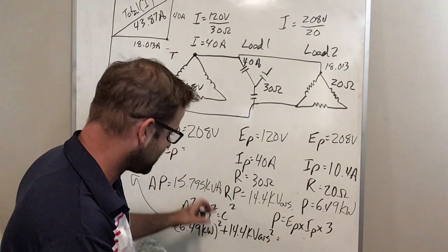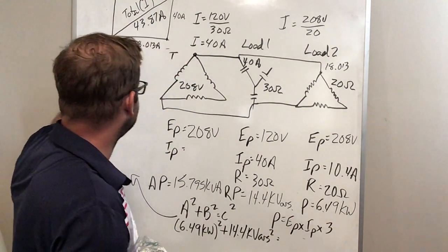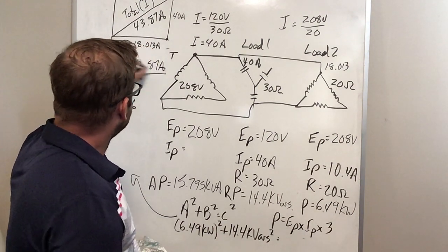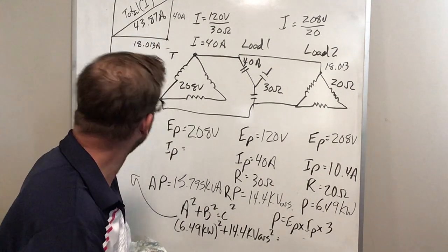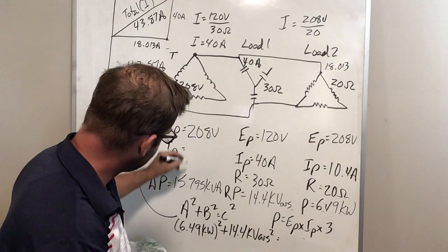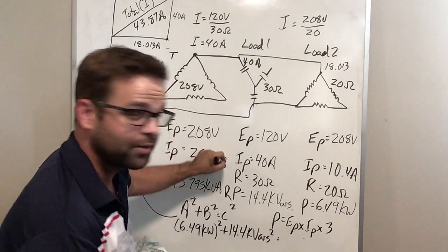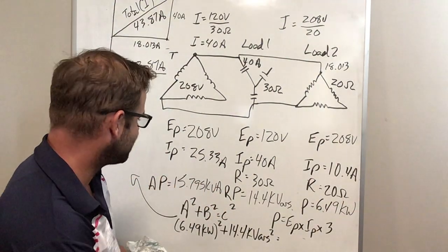And I just checked myself again, doing it backwards. It needs to be root 3 smaller. So you need to take your 43.87 amps and divide that by root 3. I'm having a lovely brain fart day. We all get those. Divided by 1.732 or root 3, and we get 25.33 amps. So if you do it around that way, you will double check yourself.